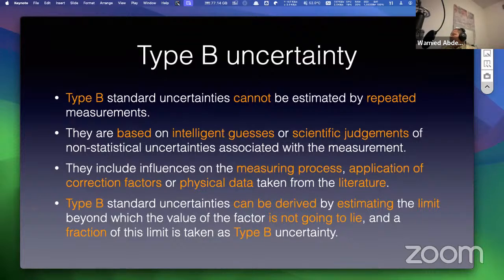We have tables for stopping power ratios, for P replacement, and so on. But these have uncertainties in them. Densities, for example, of a material. That's an example of physical data. Or, for example, the W over e, 33.97. But there is an uncertainty in that one.